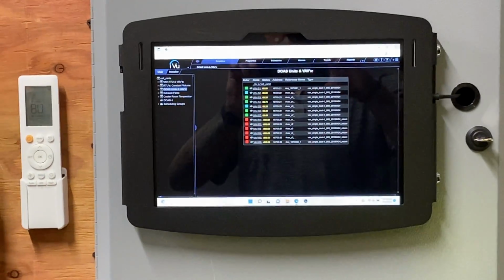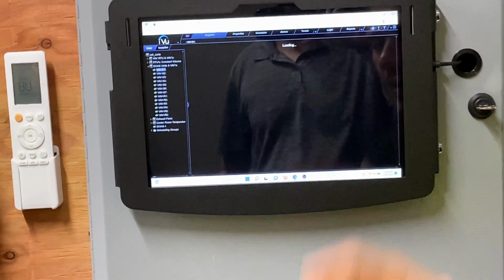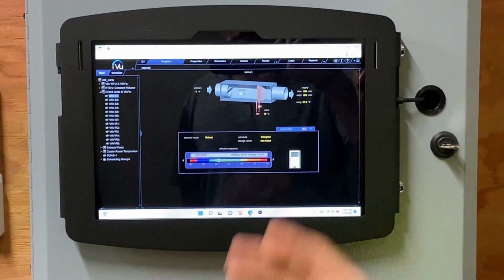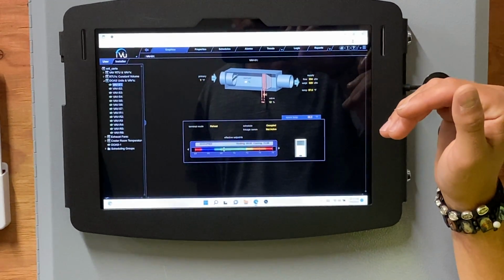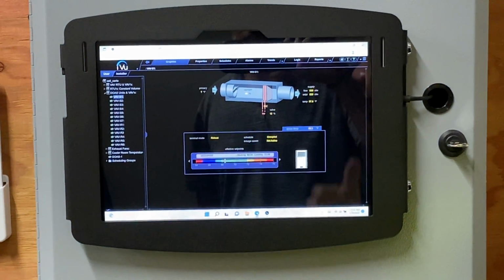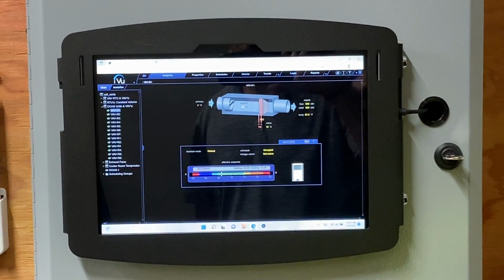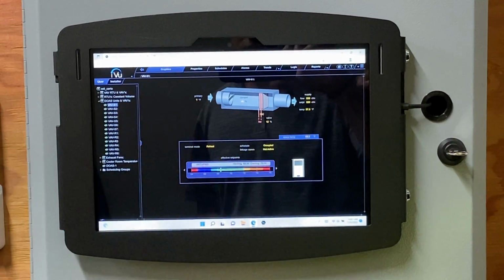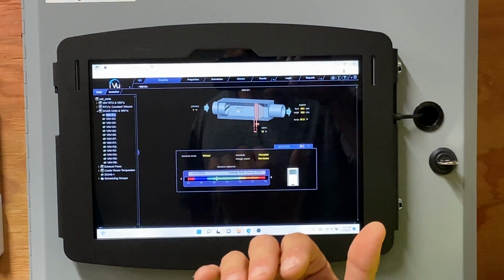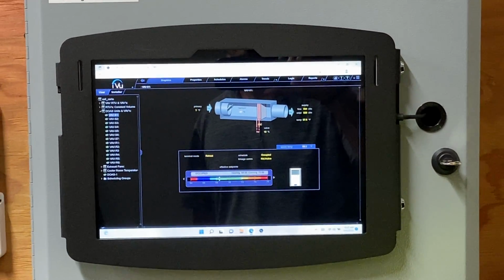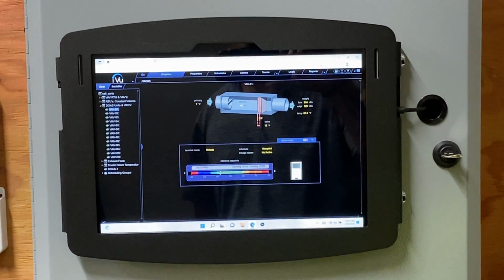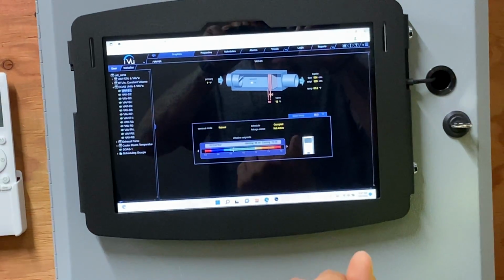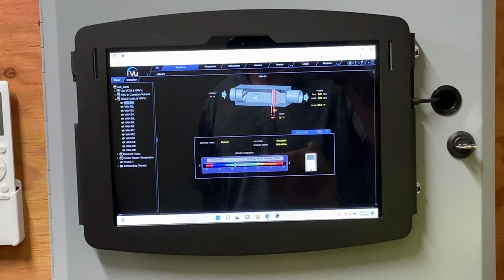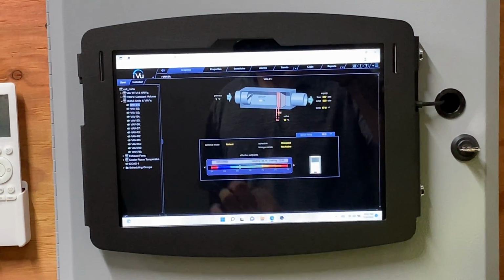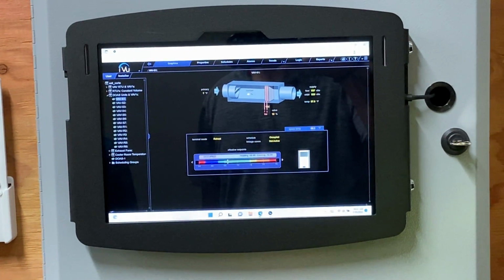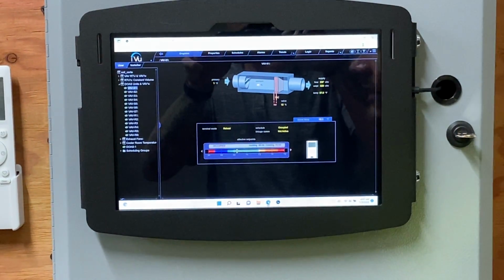That's a negative 999. Right, so on our supply side, it's just a VAV, same as I showed you earlier. We can click any of these, and it'll show what we're bringing into the room. On the return side, it's all pressure controls. You'll see I have them all finished up now. We also have actual Magnehelic gauges on each door frame next to our pressure pickup plates, each one labeled - it's a smaller silver pickup plate, no screen on it, just a screw. That's how we modulate pressure of those rooms on the return side leaving.